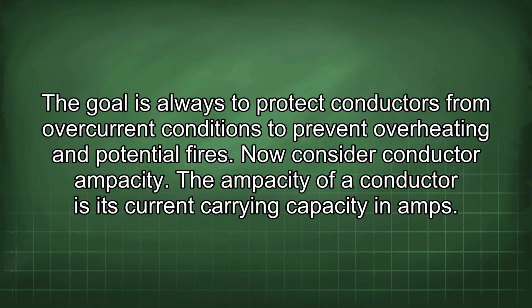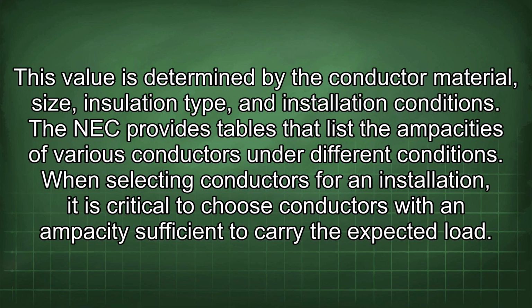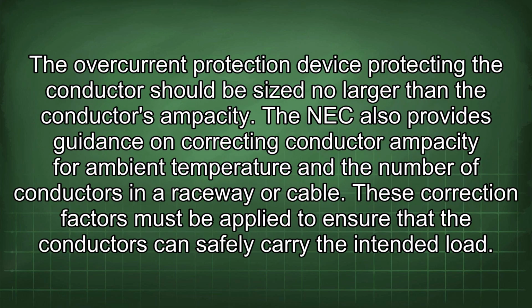Now consider conductor ampacity. The ampacity of a conductor is its current carrying capacity in amps. This value is determined by the conductor material, size, insulation type, and installation conditions. The NEC provides tables that list the ampacities of various conductors under different conditions. When selecting conductors for an installation, it is critical to choose conductors with an ampacity sufficient to carry the expected load. The overcurrent protection device protecting the conductor should be sized no larger than the conductor's ampacity.